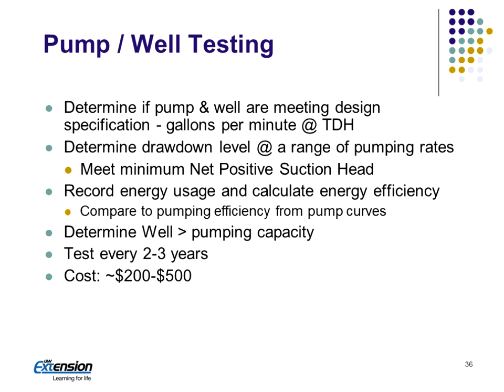To do a pumping test, we're going to determine whether the well and the pump meet the design specifications from when it was put in. Basically, gallons per minute at some total head, and whether the well can supply the water. That's another thing. We may have a pump that can pump fast, but if the water can't flow into the well fast enough, then that could be an issue where we need to do some work on the well casing itself. Sometimes you get fines up against the screen, and sometimes they put an explosive charge down in the well and try to blow the fines back away from the screen.